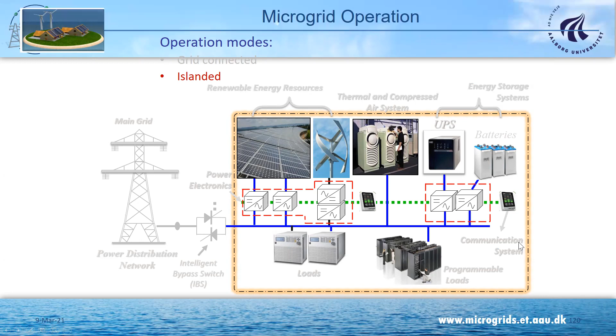So there are two ways that your microgrid can go to island. One is to have a pretty plain islanding operation. This means that I see there are some problems with the grid, power quality is not good enough, so I decide to disconnect. This is easy and safe.